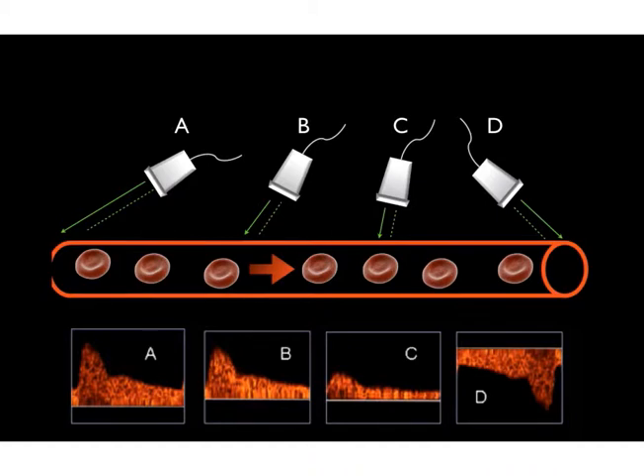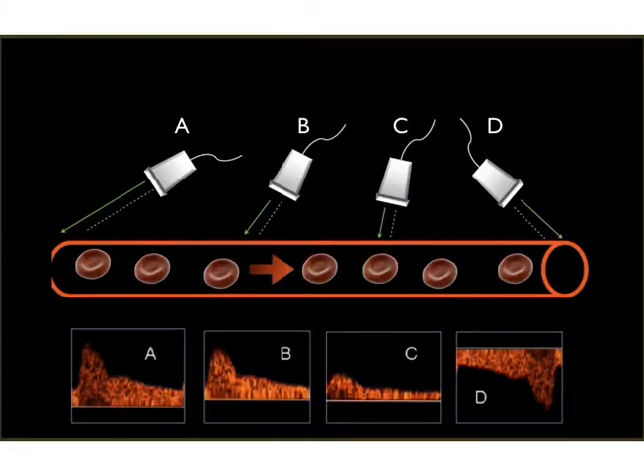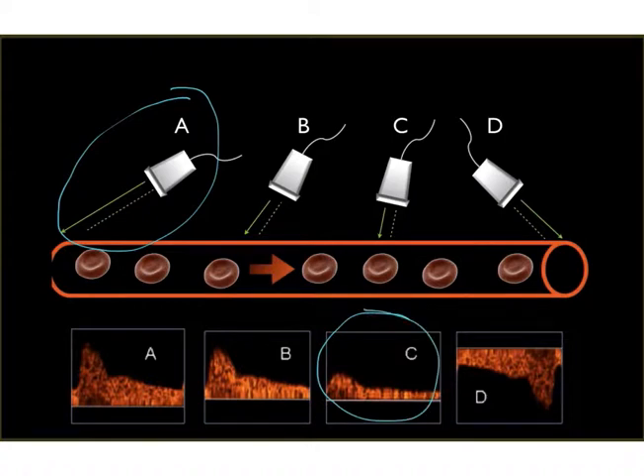So here, in this particular image, the transducer that's going to give me the greatest velocity is transducer A, because the angle is as close to parallel with the direction of flow as any of the other transducers. Now, with B and C, my angle is more perpendicular to the direction of flow, right? So because of that, my velocities are going to decrease. And you can see down here in this image, velocities in C are very small. And then velocities in D are going to be completely reversed. They're going to be going the opposite direction, and that's because now the blood cells are moving away from the transducer itself. So why am I telling you all this?